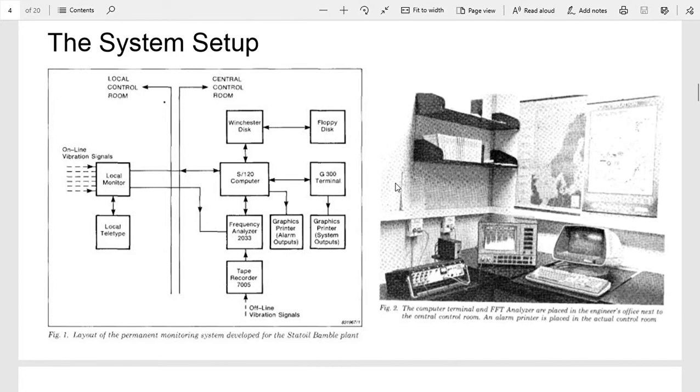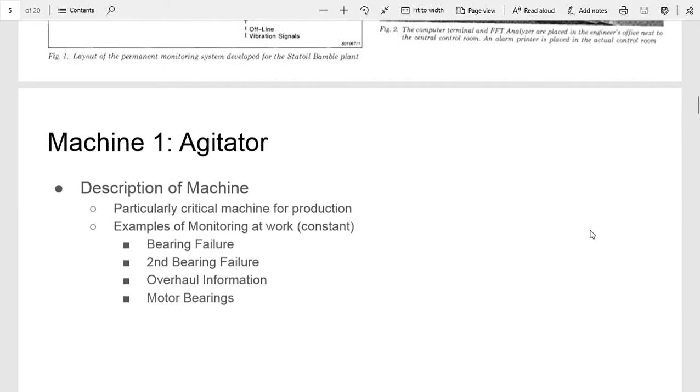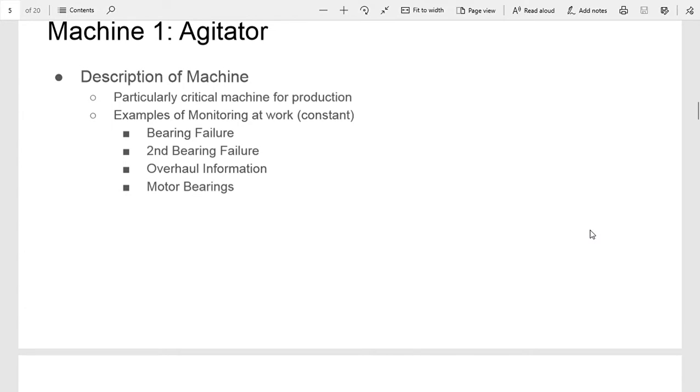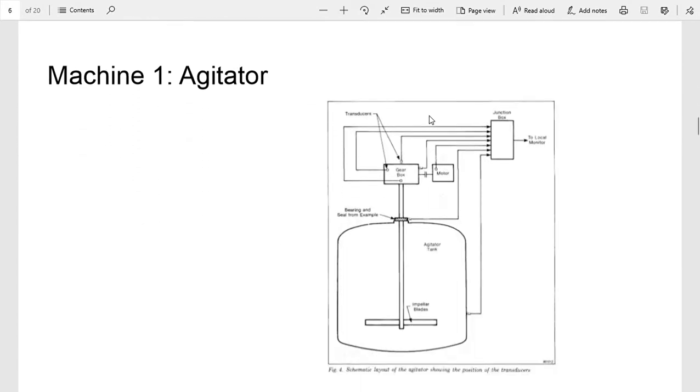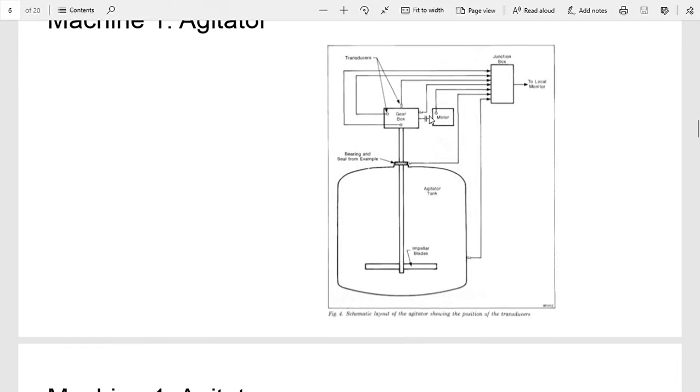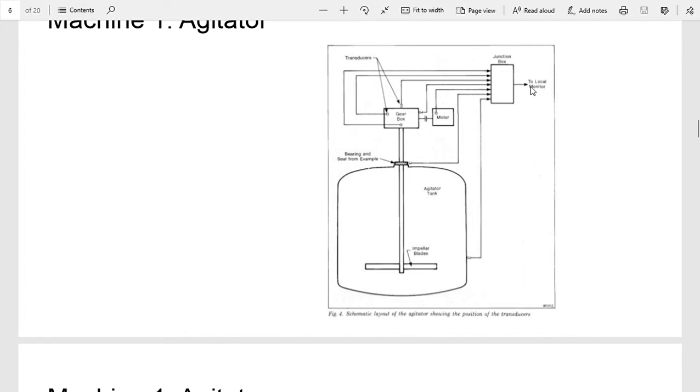This was the setup they had for analyzing. So the first machine was the agitator, and basically the agitator is a large mixer. This is one of their most critical machines for production. Here's a little graphic of the agitator: big tank, mixing blades, gearbox, motor, and then each one of these little circles is one of the accelerometers in various places, all sent back to the monitor.